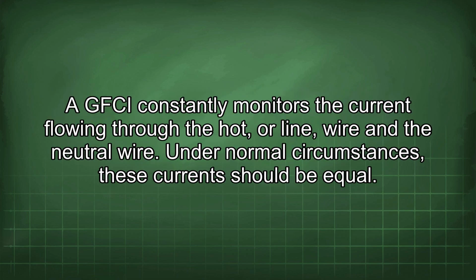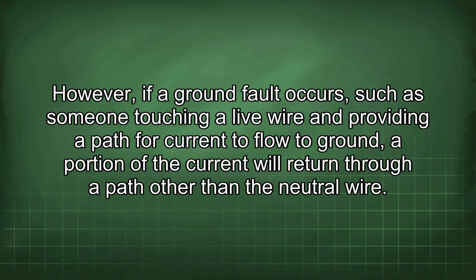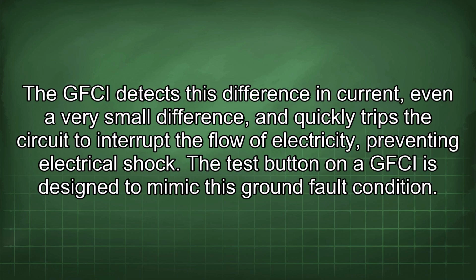A GFCI constantly monitors the current flowing through the hot, or line, wire and the neutral wire. Under normal circumstances, these currents should be equal. However, if a ground fault occurs, such as someone touching a live wire and providing a path for current to flow to ground, a portion of the current will return through a path other than the neutral wire. The GFCI detects this difference in current, even a very small difference, and quickly trips the circuit to interrupt the flow of electricity, preventing electrical shock.